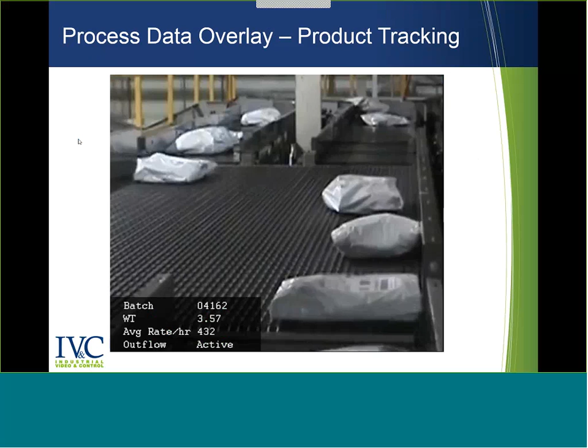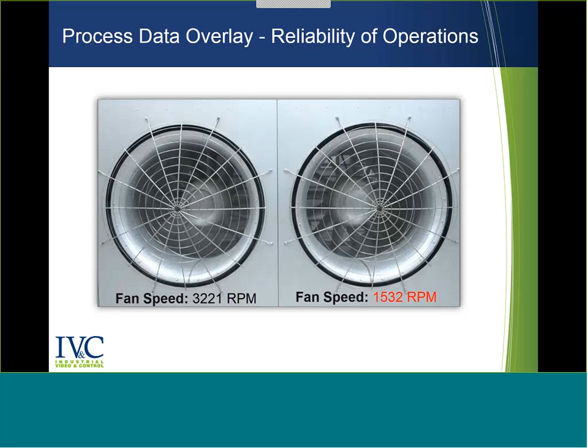This is a video clip showing two different fans, where we're overlaying fan speed. In LongWatch, you can set threshold tables or limits, and if the data gets above or below that limit, we can change the font color or draw a circle around different components to alert the operator and give more context about what's happening with that piece of equipment.